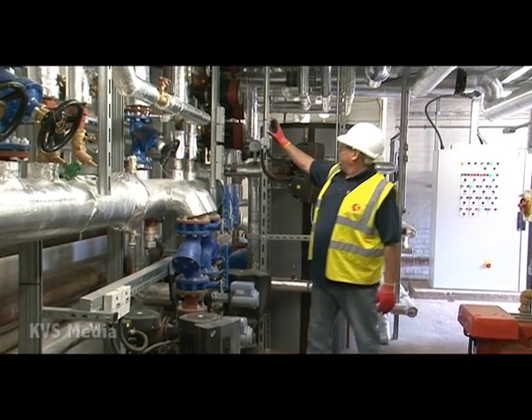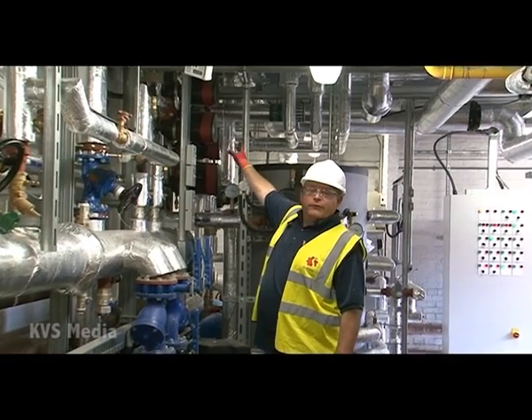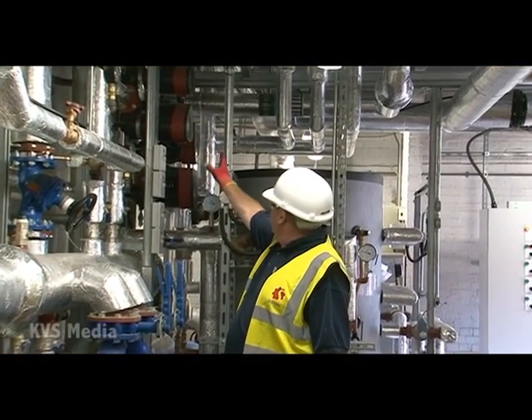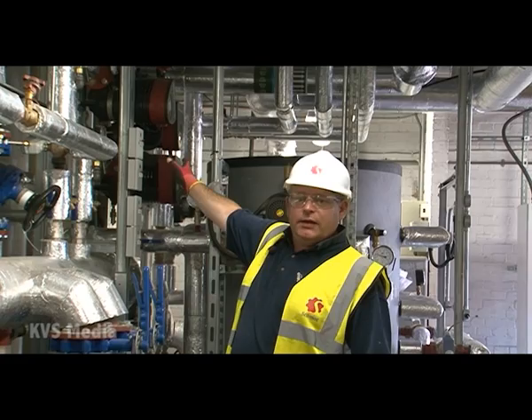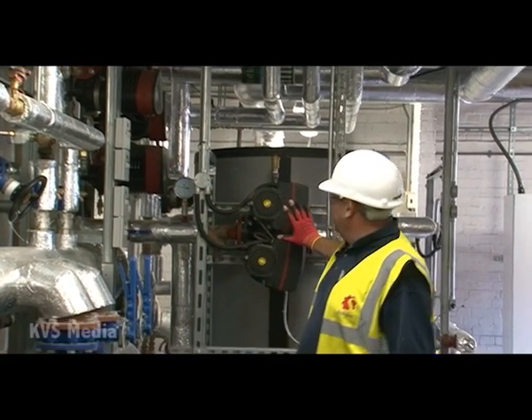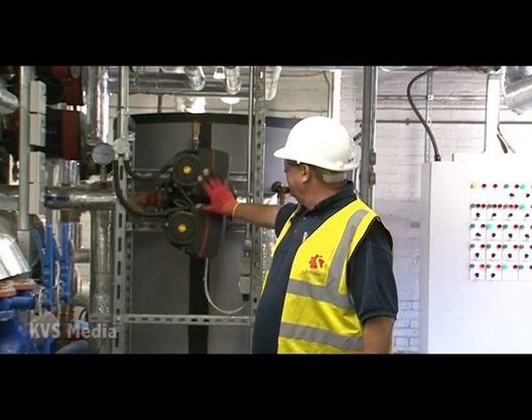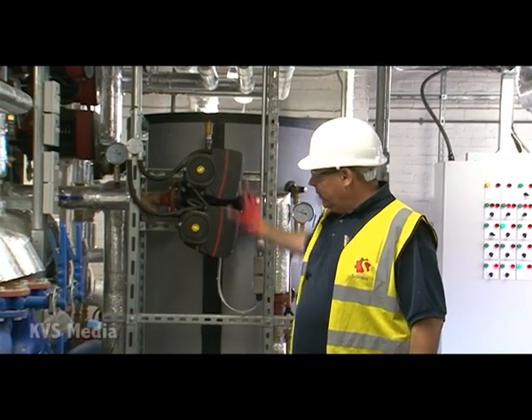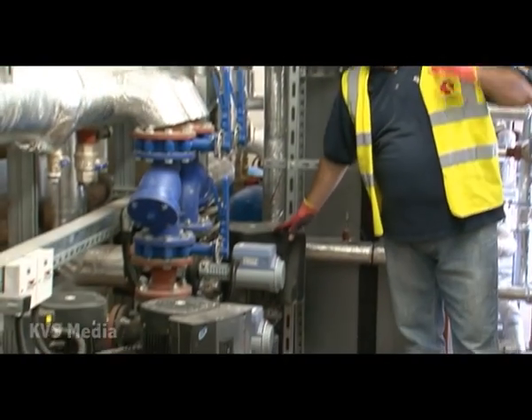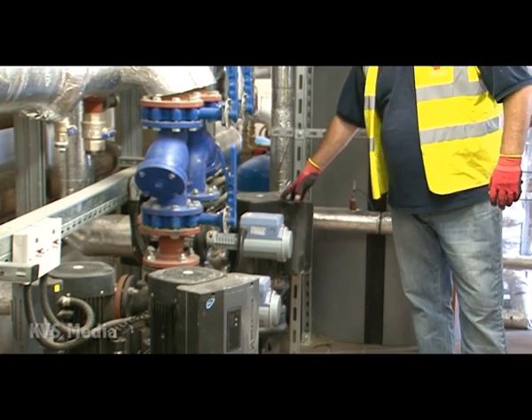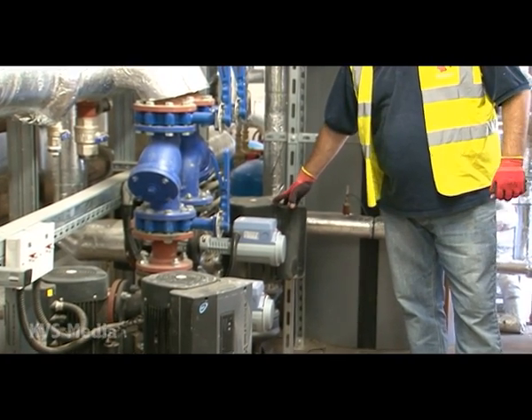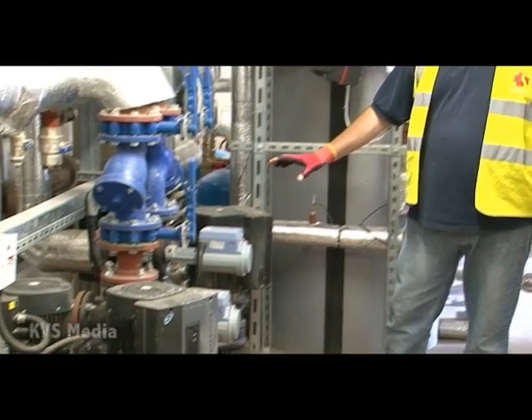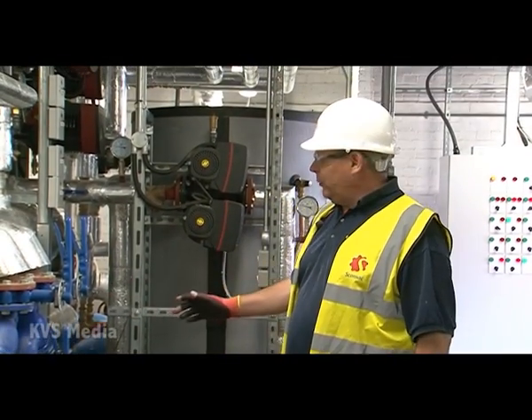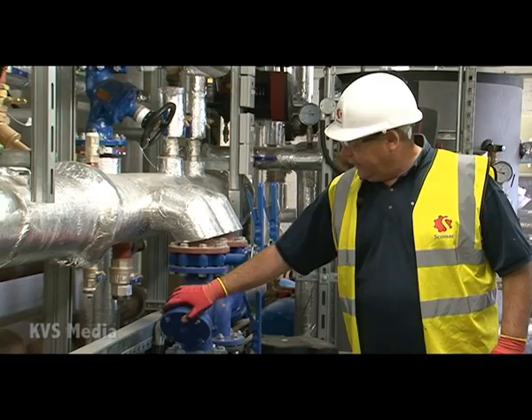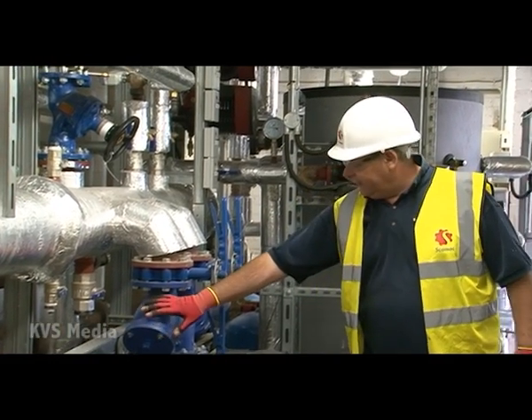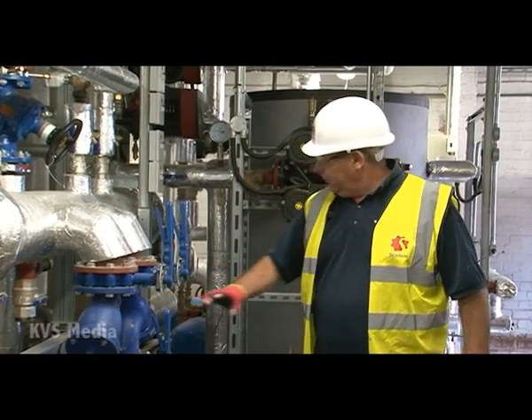We then go back through, we have the 2 pumps at the top serve the kitchens. The 2 pumps below it serve block B. We then have 2 pumps here which do the hot water. This is the hot water to the 2 new cylinders. We then have the next set of pumps down which serves block A and also the hairdressers, which they call block C. Maintenance wise, the only bits of maintenance in the plant room are the heating strainers, which are these two items here, one for block A system, one for block B system.